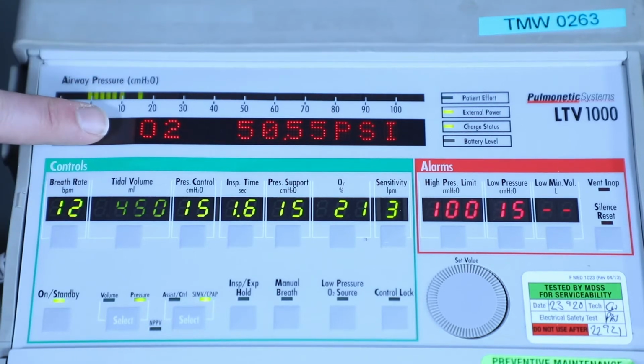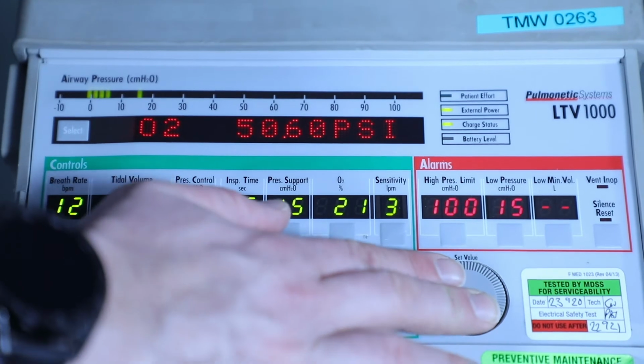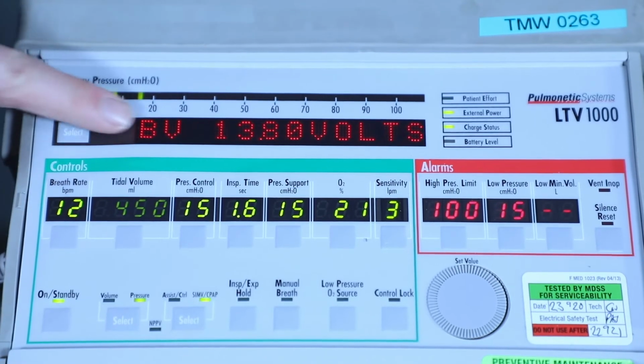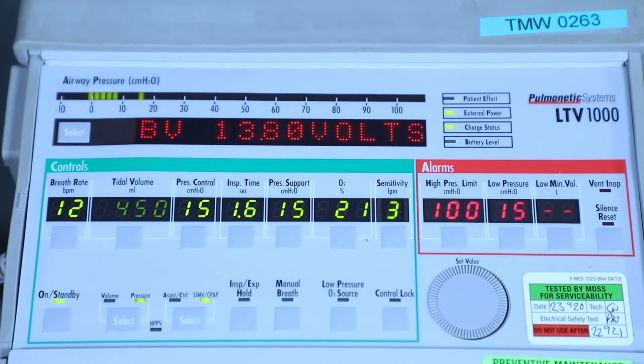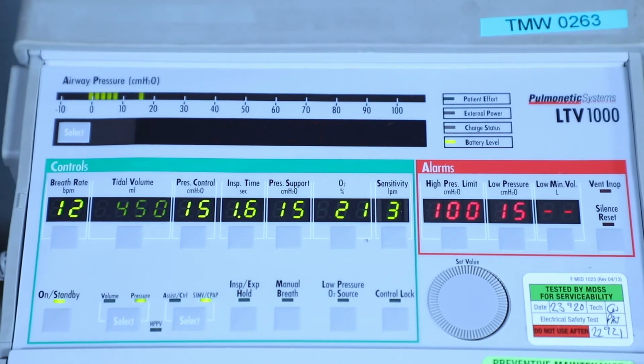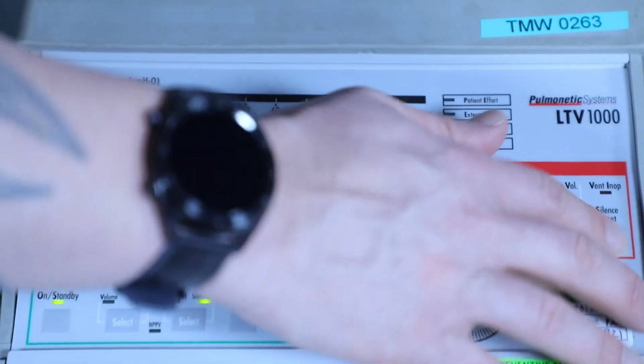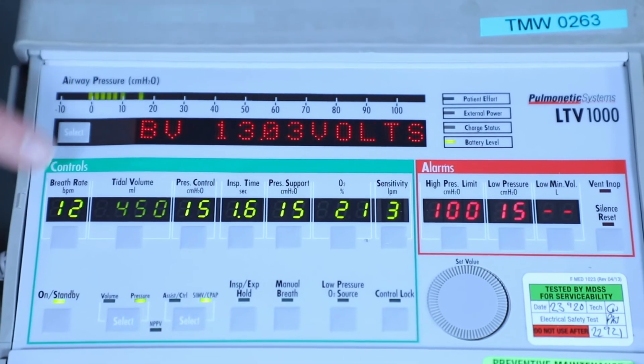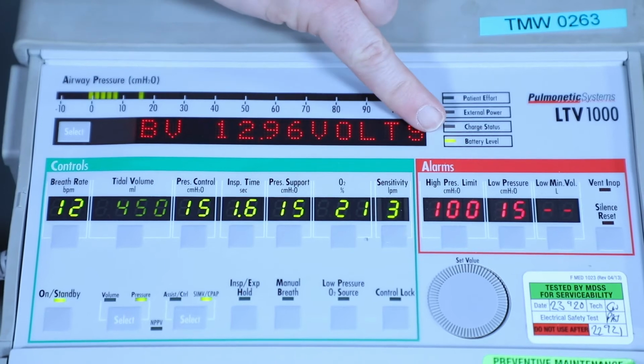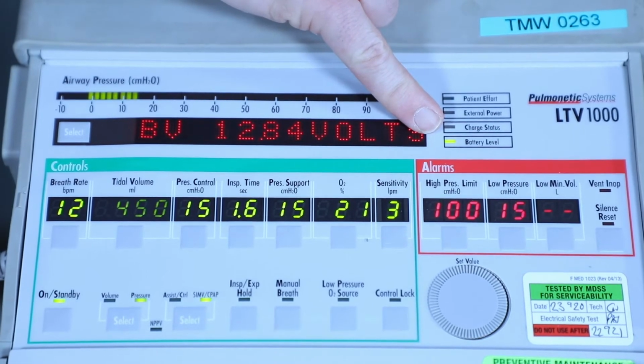We now want to check the internal battery. So if we scroll to the right, you can see the battery voltage. This is the battery voltage for the mains adapter. So if we disconnect, it should say power has been lost. We can silence and reset this. What we also notice on the battery level, we're now switched to internal battery.